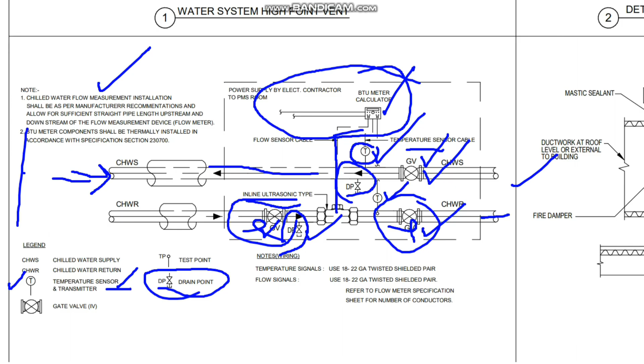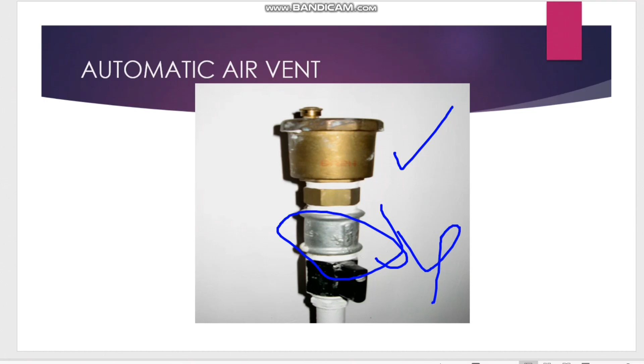Normally in the water side HVAC system, similar to this arrangement, lots of accessories will come, like automatic air vent and drain connection. For example, at the riser side, at the top of each riser, this is the riser connection for our case. At the top of each riser, that means at the roof level, normally we can see the automatic air vent installed at this point. The automatic air vent has to be provided at the top of the riser, and below also we will provide the drain connection. This automatic air vent we must have with one isolation valve. For example, below the automatic air vent we will have one isolation valve. If you want to do any maintenance, we can close the isolation valve and do the maintenance on the automatic air vent. After the automatic air vent we can see the drain valve also.